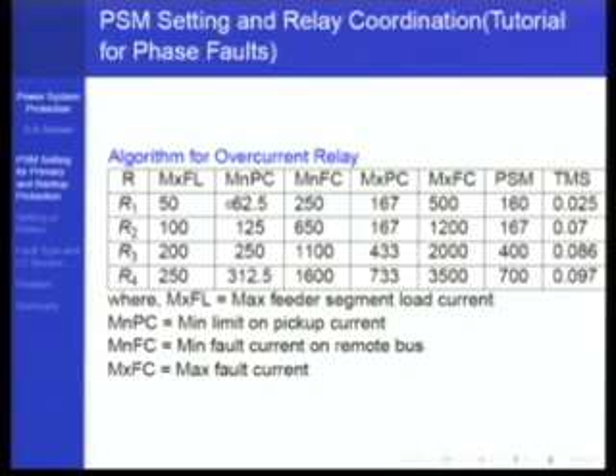Then, as I said, for the pickup current, we are not setting the earth fault relays right now, we are setting the phase relays. The pickup of the phase relay should be at least 1.2 times the maximum load current, so that it never operates on load current. Therefore pickup is set to 62.5, 125, 250, 312.5, that is 50 times 1.25, 100 times 1.25, and so on.